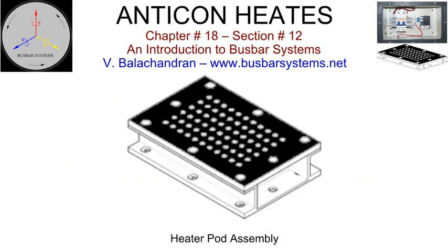To maintain the desired temperature of the air inside the enclosure, heater pods are provided at strategic locations along the route in each phase. Heaters are also accommodated as close to the insulators and bushings as possible. Heaters can be installed at the insulator base with modified support castings. The sizing of the heater element and setting of the controlling device, such as the thermostat, humidistat, or hygrostat, will depend upon variations in the ambient conditions and trapped volume of air inside the isolated phase bus.